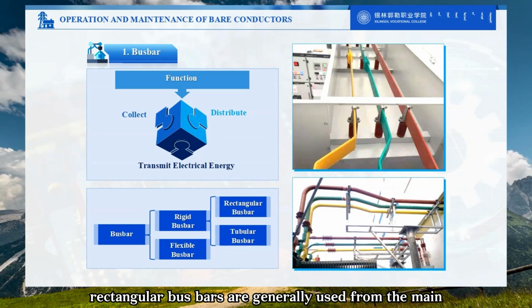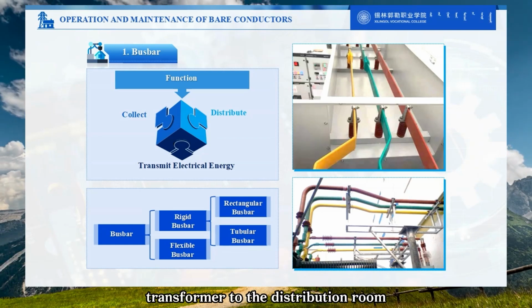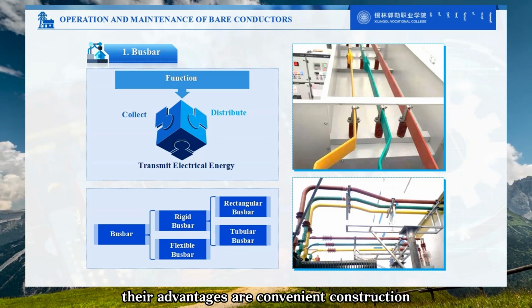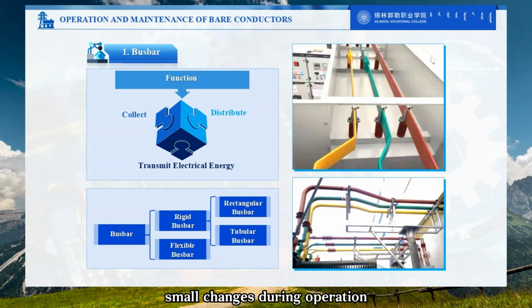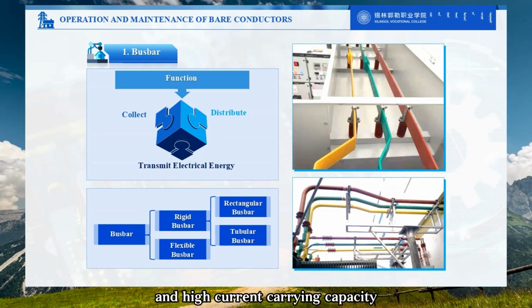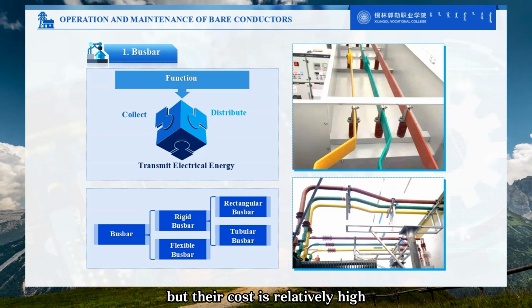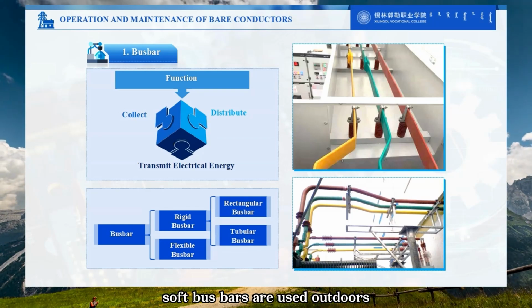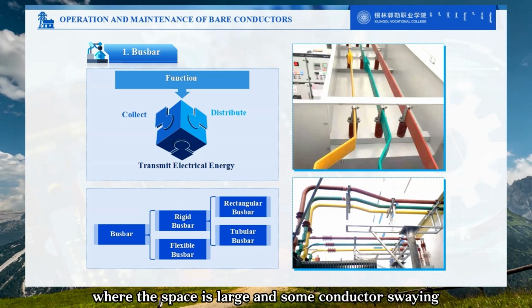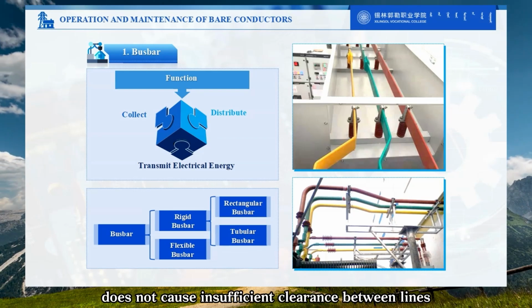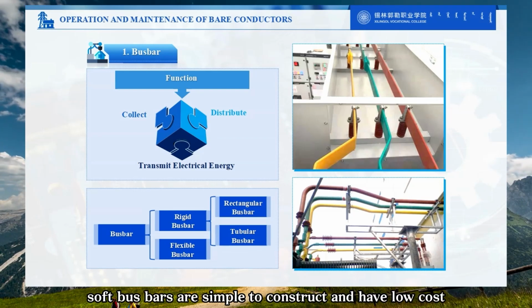Rectangular busbars are generally used from the main transformer to the distribution room. Their advantages are convenient construction and installation, small changes during operation, and high current carrying capacity. But their cost is relatively high. Soft busbars are used outdoors where the space is large and some conductor swaying does not cause insufficient clearance between lines. Soft busbars are simple to construct and have low cost.